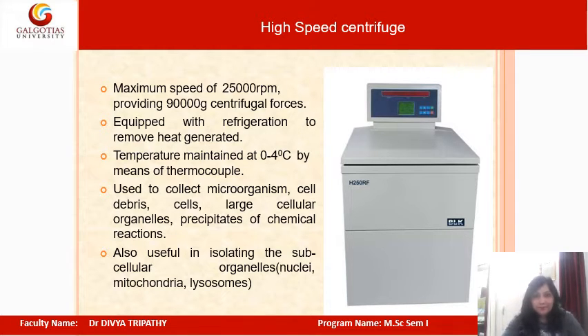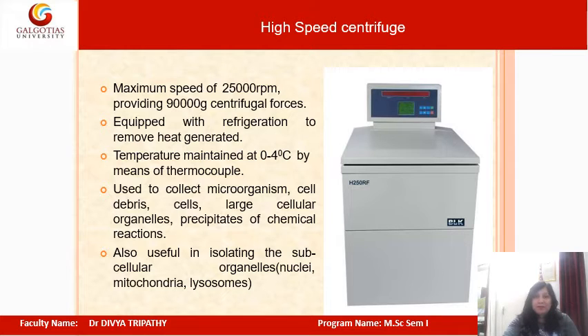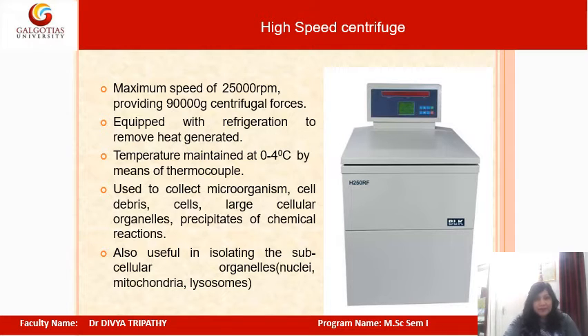High-speed centrifuges exist in efficiency between ultracentrifuges and desktop centrifuges. They have a maximum speed of 25,000 RPM, providing up to 90,000 G of centrifugal force. They are equipped with refrigeration to remove heat generated during operation, maintaining temperatures of 0 to 4°C by means of thermocouples. These are used to collect microorganisms, cell debris, large cellular organelles, and chemical precipitates, and are also useful in isolating subcellular organelles like nuclei, mitochondria, and lysosomes.